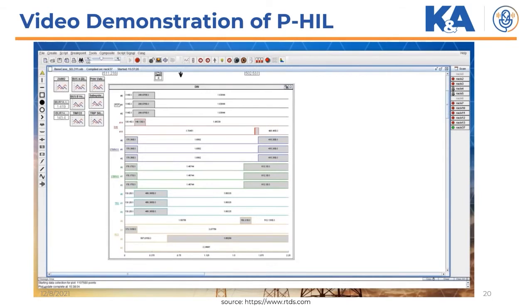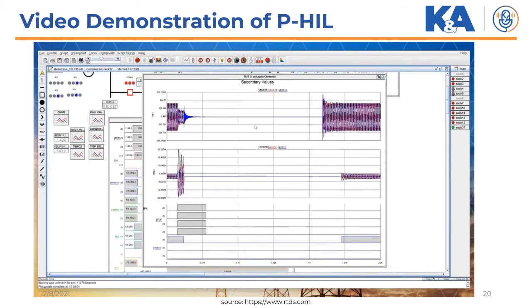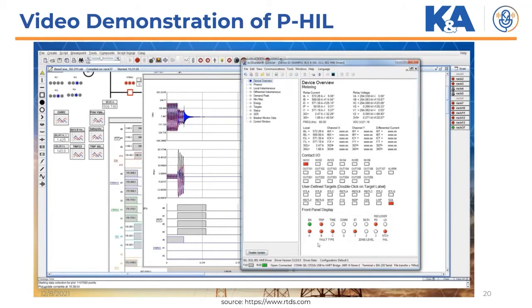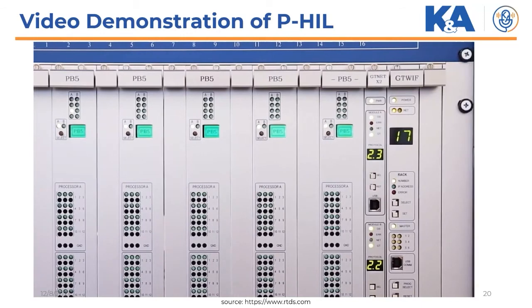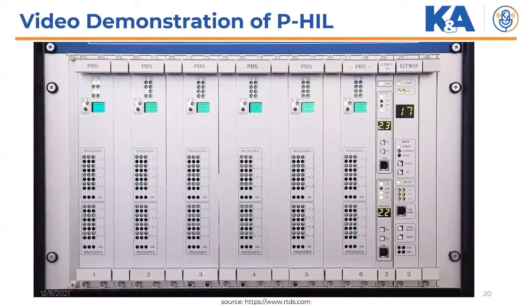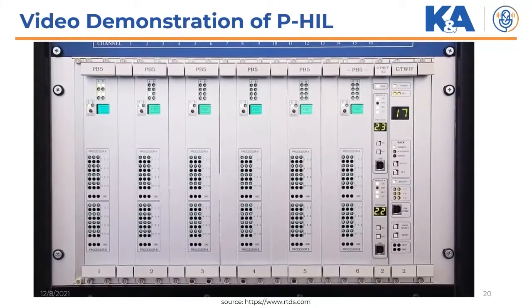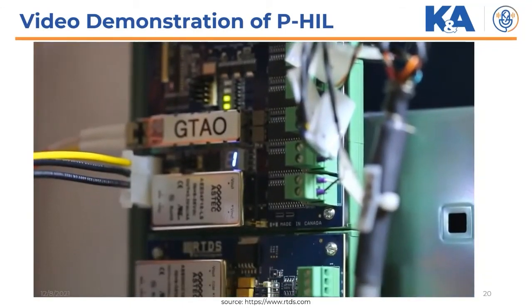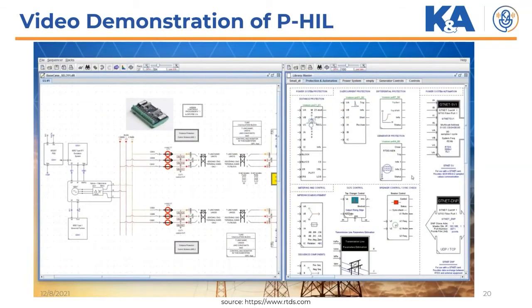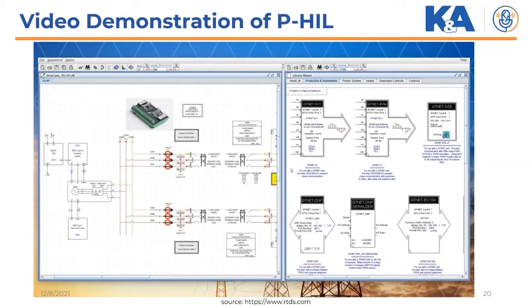Protection testing with the RTDS simulator can also be conducted using an IEC 61850 interface. The RTDS simulator's GTNet X2 network interface card allows the simulator to communicate with the physical relay using LAN-based protocols. As an alternative to using the GTAO card for analog output, the current and voltage signals from the simulation case could be sent to the relay using IEC 61850-9-2 sampled values data. The breaker commands and status could be communicated via IEC 61850 GOOSE messaging.